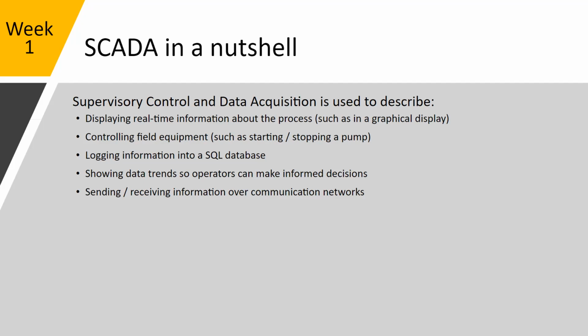live data, especially when you get into water, wastewater, you're going to be having to retain this information for the Ministry of Environment. One of you guys were saying you did some work in the food and beverage industry. A lot of your clean in place systems typically have to have regulated temperatures met for certain amounts of time. This information is going to be stored in a SCADA system somewhere. It's going to be put into a historian so that you can prove you've met your cleaning cycles for any sort of audit. Again, showing trending so operators can make informed decisions, and then sending and receiving different information.